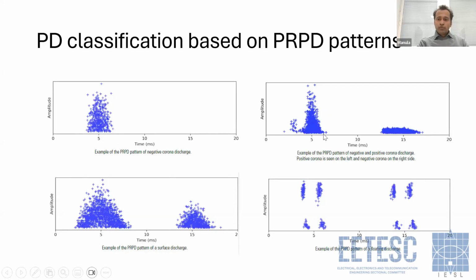When it comes to positive corona, it is always accompanied by negative corona. As I said earlier, whenever there is a positive corona, you would see negative corona as well, and the negative corona has a higher strength than the positive corona. And the third PRPD pattern shows the surface discharge. It would have clusters both in the positive half cycle as well as in the negative half cycle. There might be two different strengths, or both clusters might have similar or identical characteristics, depending on the type of surface discharge.